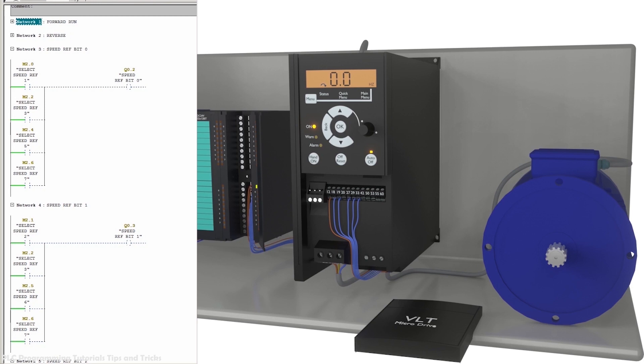Now we upload the program into the PLC and monitor the ladder logic. First we turn on the M0.0 run command bit — it turns on PLC output Q0.0 and sends a digital signal to the run input terminal of the VFD. Next we turn on M2.0 (select speed reference 1), which turns on Q0.2 (speed reference bit 0) and the VFD loads preset frequency reference 2.5 Hz. The motor starts running at 2.5 Hz.